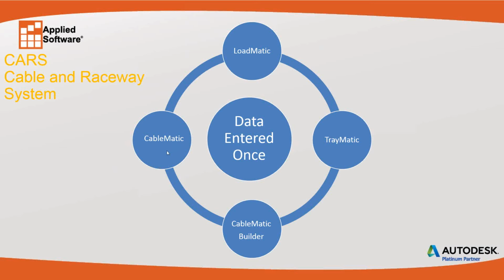Once our raceway is complete and our cable origins and destinations are complete, along with the cable size and voltage level, the program will automatically route our cables through the raceway based on origin and destination as defined in the Cablematic table. Once we've done this, we'll be able to do tray fill calculations, conduit sizing and fill calculations, material takeoffs on cable, cable tray, and conduit, and get many various other reports, including voltage drop calculations based on the load plus the length.